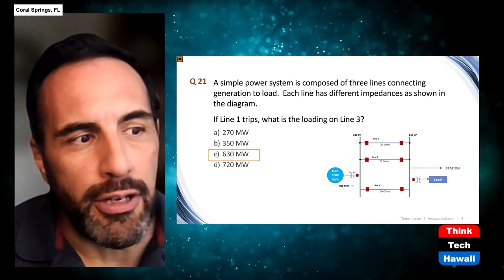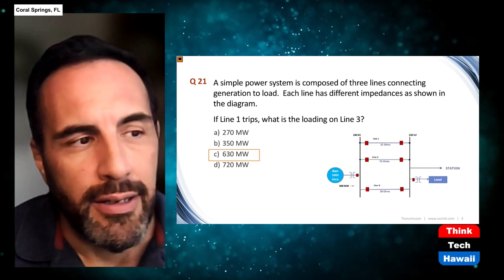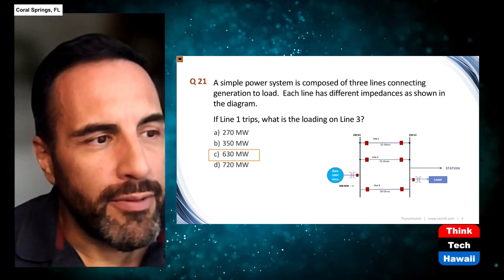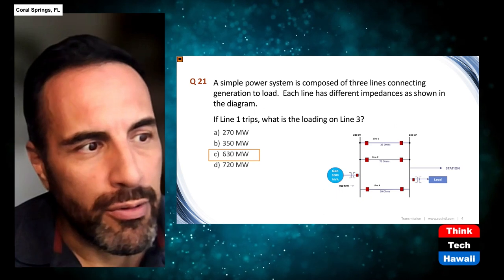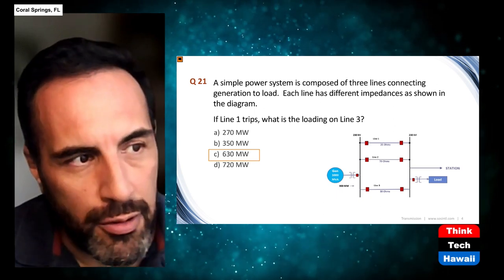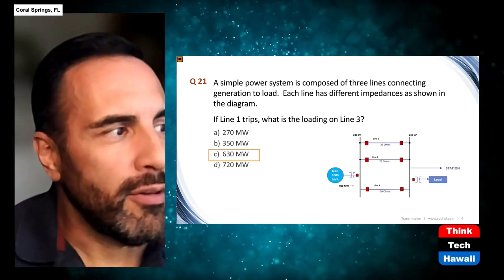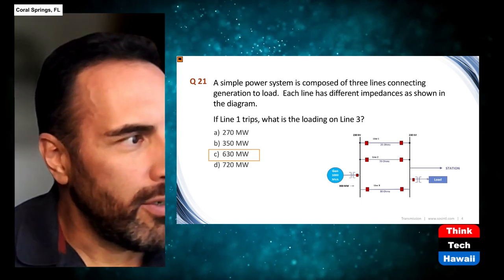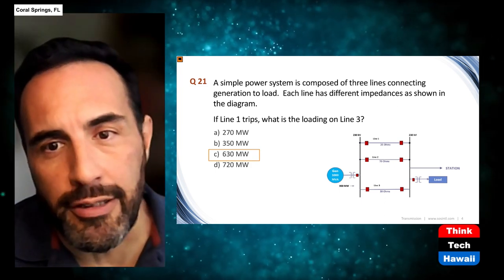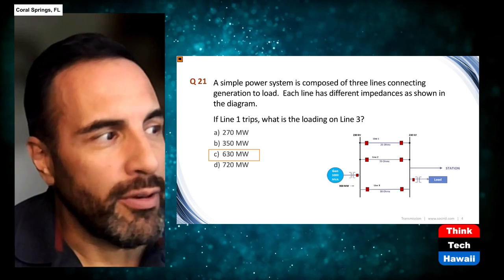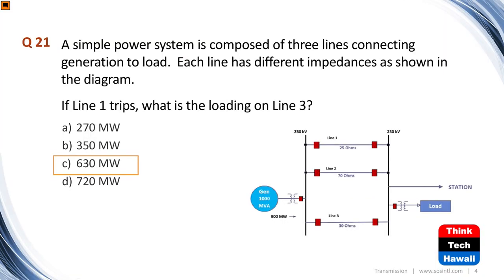So if you have 30 ohms on that line, it's likely that 70% of the flow will go through line three, and 30% of the flow will go through line two. Hence, you do the math, breaking this down proportionately based on the impedances. So again, the answer here is C, 630 megawatts will be flowing on line three.